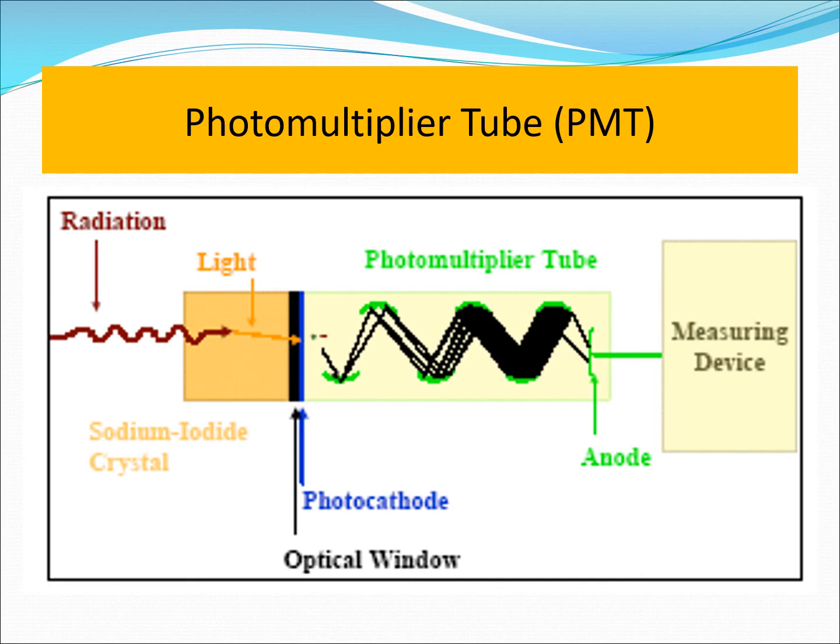This is another schematic of the photomultiplier tube. Radiation interacts with the scintillator and produces light photons, which come into contact with the photocathode. It releases electrons, which converge on the first dynode, the greenish colored component, and that is amplified on the second dynode and further amplified on the third, and so forth, until at the very end towards the right, the amplification has reached a level where it can be produced into signals as displayed towards the end.